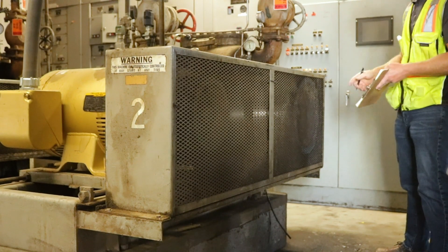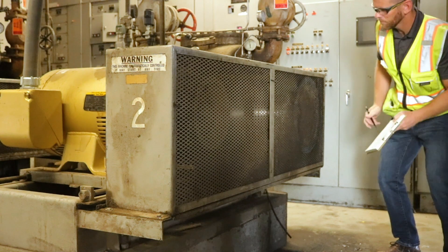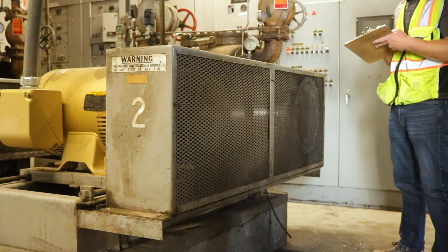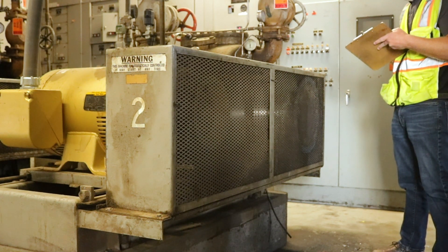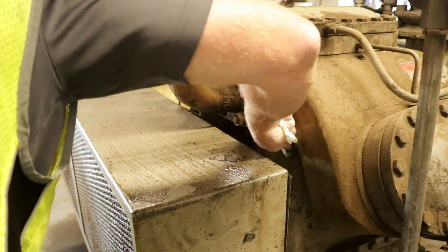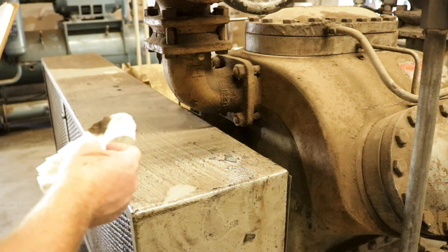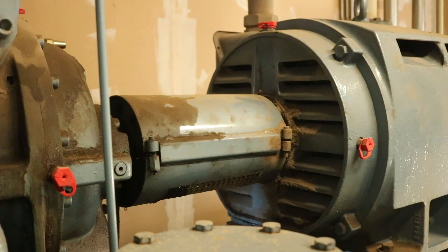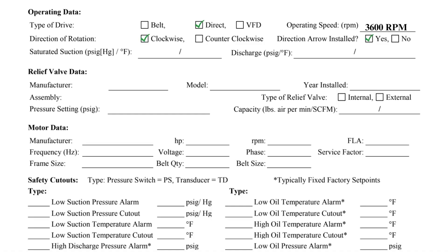This recip compressor is belt driven. The operating speed is 1,200 rpm, the direction of rotation is clockwise, and there is no flow direction arrow installed. Essentially all screw compressors are direct drive at 3,600 rpm.